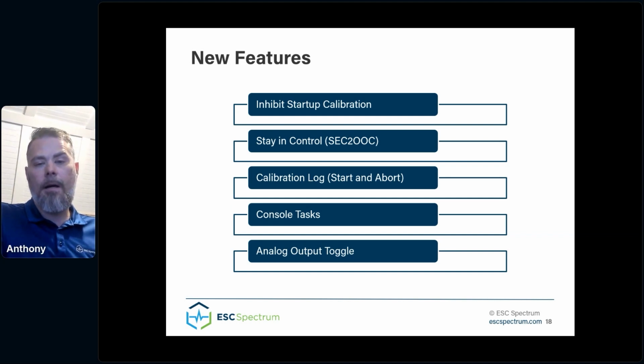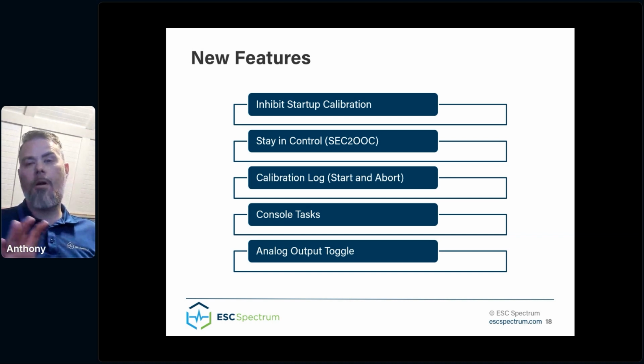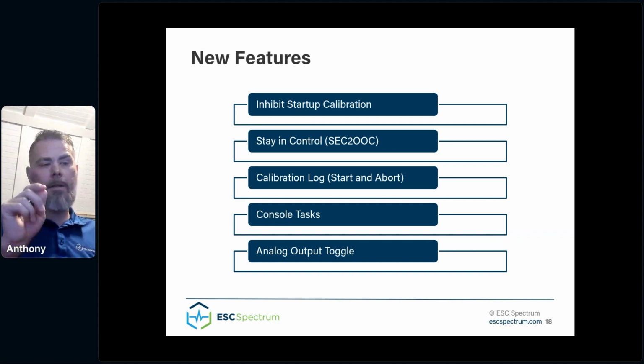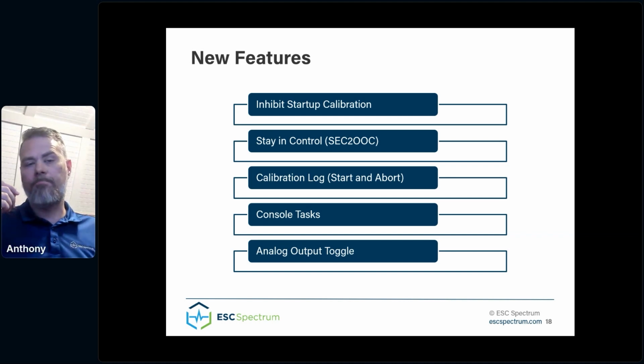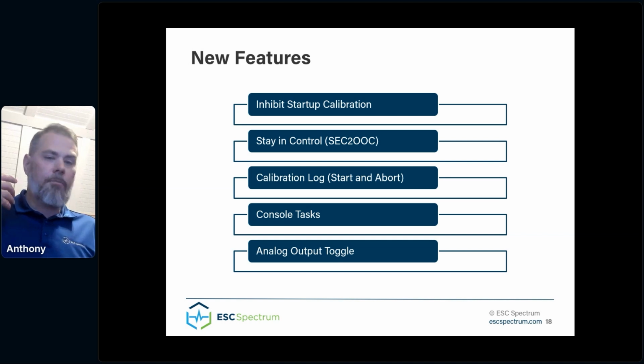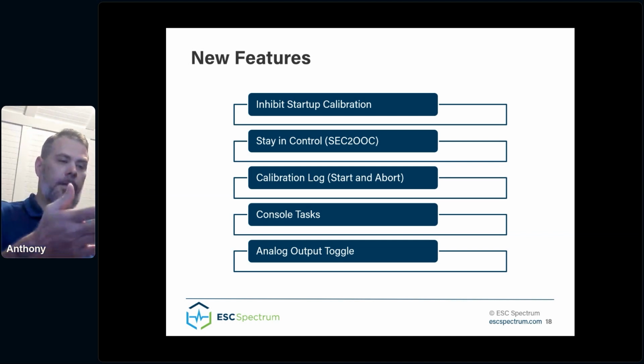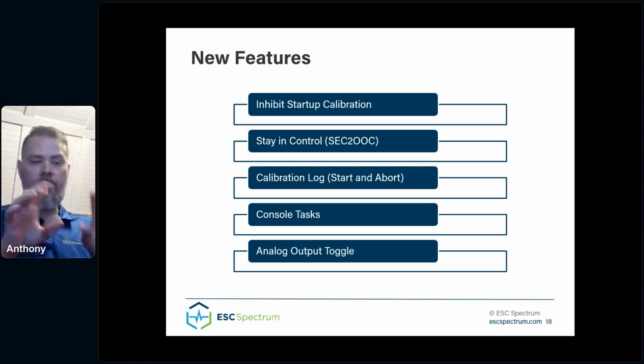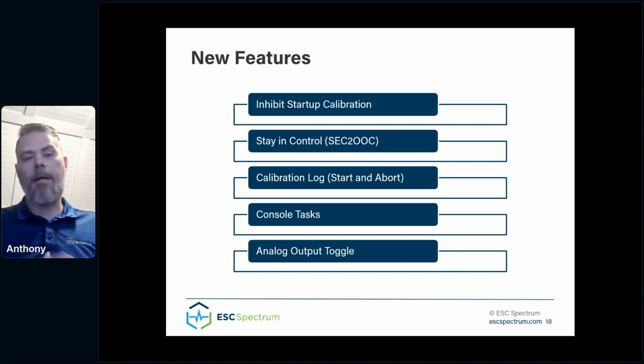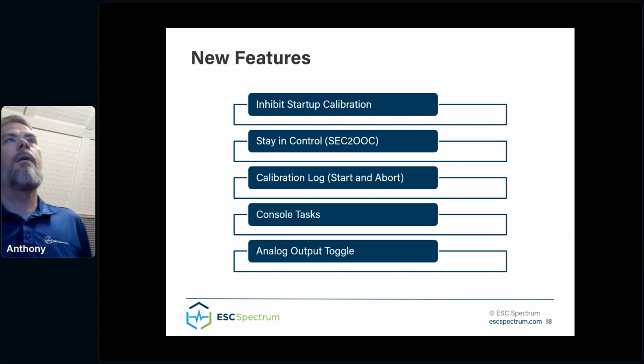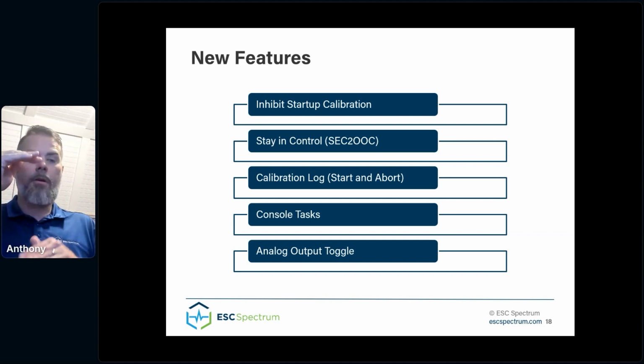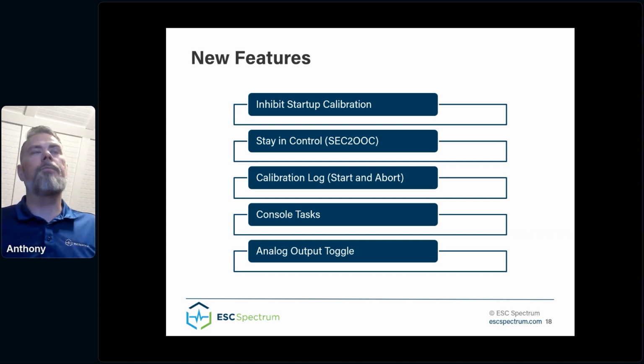We added an MDI menu that is a log of calibrations showing how they were initiated, whether from a remote client issuing a dashboard command to start the cal, done manually, or started by a digital trigger. You can now go into the calibration log and see when calibrations were started, and also see if a calibration was aborted by a user.